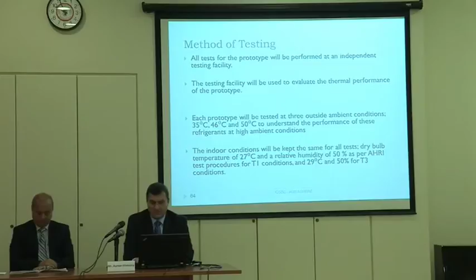So we'll test in an independent lab. We're all going to be testing the same thing for the thermal performance. And we're going to be testing those machines at 3 different temperatures, 35, 46, and 50, to really see the curve and to make sure that we understand the behavior of the machine in this range of temperature. And the indoor temperature, Ayman has mentioned, we're going to go with the standards of AHRI and with ISO on how to test them and so on. Endurance tests will be done according to standard.